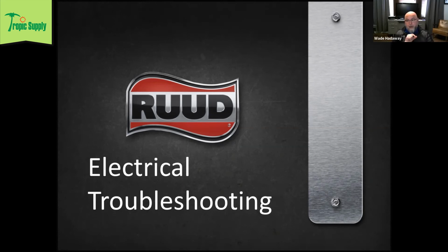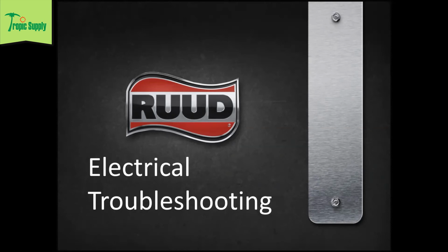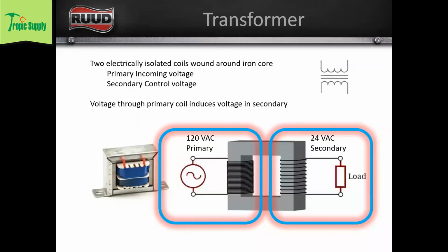Sometimes that can be because you have an undersized wire. It could be because your runs are too long. It could be because you have a couple of loose wire nuts. It could be because under a full load, say a heat pump, for example, where we've got several things going on at once, we could be having some trouble with that electromagnetic field. And then on your last slide, I thought you said earlier that it was current, not voltage, that generates the field.